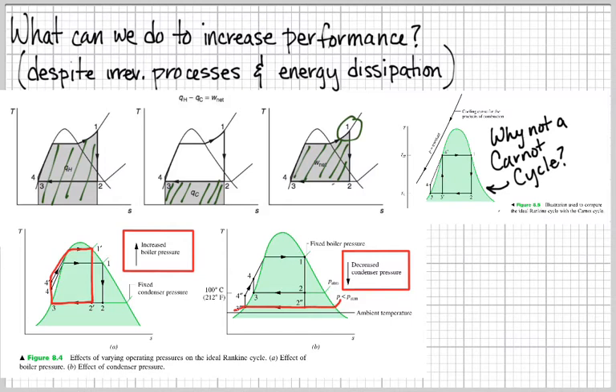If I have a low quality steam it means that I will have water droplets in my steam that will abrade or effectively gouge out over time the protective surface of the turbine blades, thus exposing by physical abrasion the surface to corrosion. We have erosion that leads to corrosion and electrochemical corrosion rusting, then the blades work less and less well and you have to shut the turbines down.